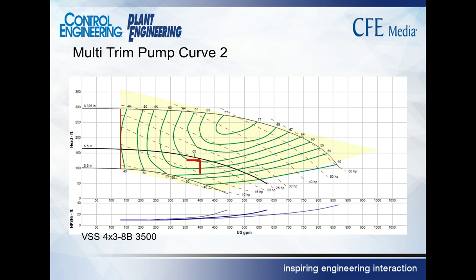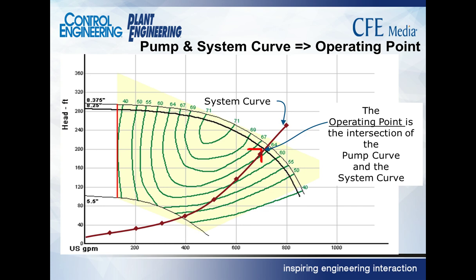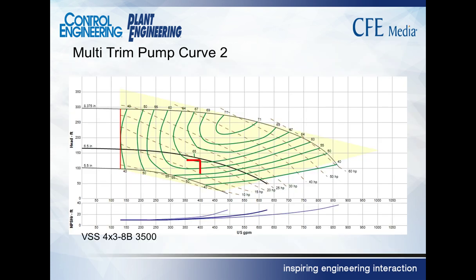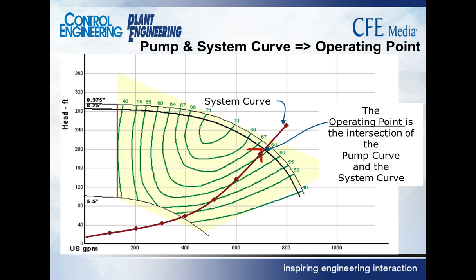So when sizing pumps, it's a lot different than sizing a lot of other machinery. It's got to be the right size, not too big. So where a pump actually operates, for instance, why does this pump operate at 400 gallons per minute and 125 feet of head? That's determined by the system curve.